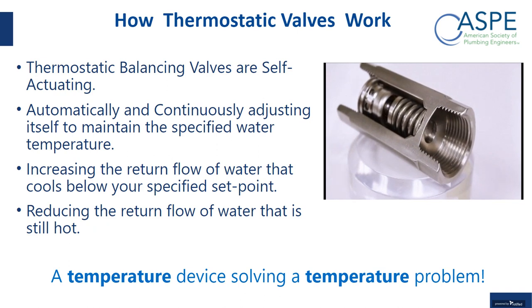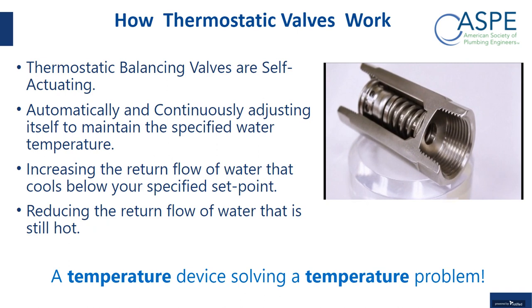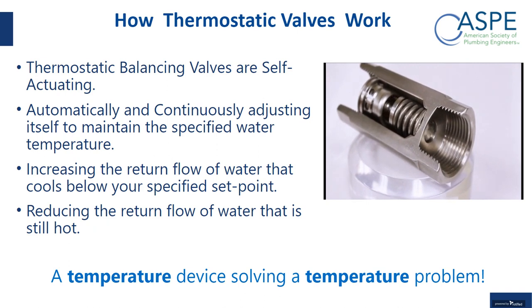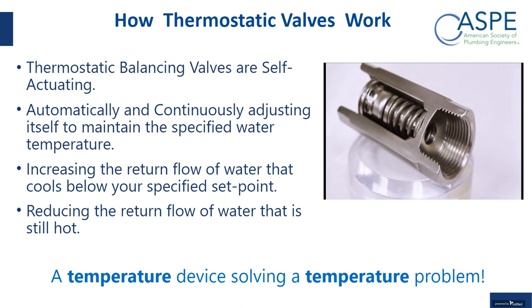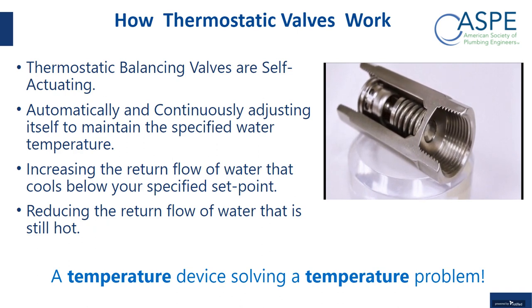At 120 F, the valve is in that closed position, that bypass position. At 110 or less, which is a 10 degree span, the valve is in a full open position. So this valve will modulate open to closed over 10 degrees Fahrenheit, and it will continually do that. As conditions change in a building for whatever reason, where you may need higher flow to offset heat loss or less flow, this valve will adjust its position accordingly.